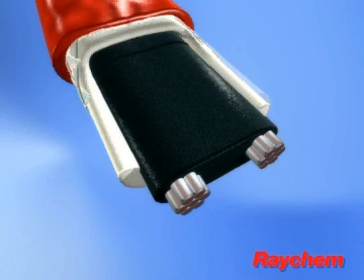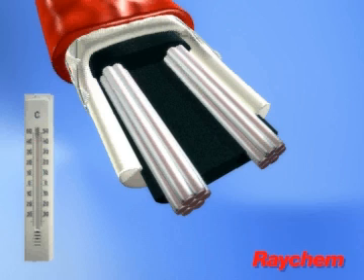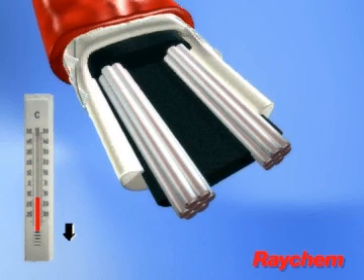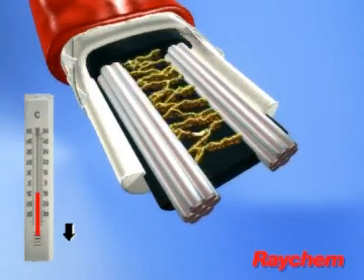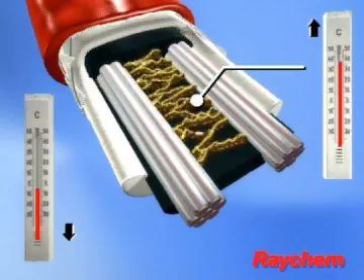But the magic happens in the conductive core that surrounds the two parallel conductors. As the ambient temperature drops, the core contracts microscopically and the number of electrical paths through the core increases. More heat is produced.